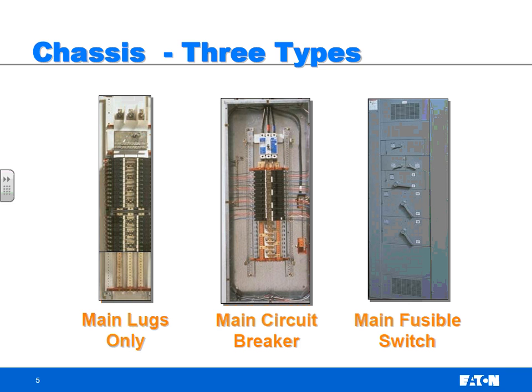And they do that because if you have a high fault current, the number one thing at that point is safety, get something open. If I don't open the circuit breaker, you've got a good chance that the contacts inside here may actually weld together. And if those weld together, it could happen to all the other circuit breakers in there. And then you've got a fault current and nothing's opening, and then it can get real dangerous.